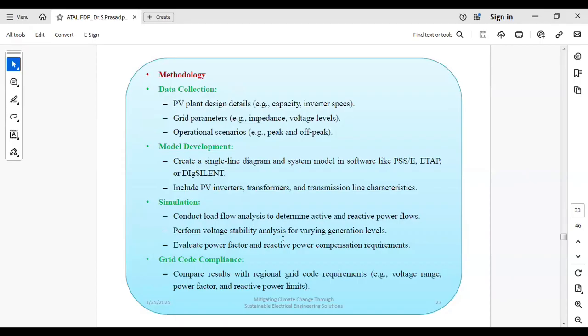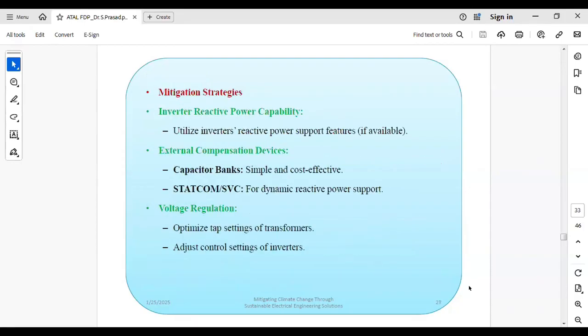Basically, reactive power analysis is nothing but load flow analysis, and you have to conduct load flow analysis for reactive power analysis, and a voltage analysis test to check whether you are able to maintain voltage at the point of interconnection or not. Okay, so these are the solutions: compensating devices we are using, capacitor banks, STATCOM or SVC, and sometimes we use tap setting transformers also to adjust the voltage.